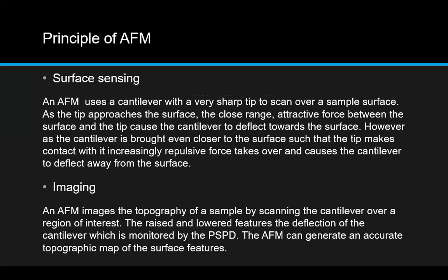However, as the cantilever gets even closer to the surface, the tip makes contact with increasing repulsive force and causes the cantilever to deflect away from the surface. Second is imaging. AFM images the topography of a sample by scanning the cantilever over a region of interest. The raised and lowered features cause deflection of the cantilever, which is monitored by the PSPD. The AFM can generate an accurate topography map of the surface features or structure.